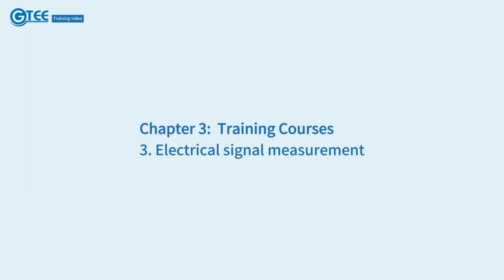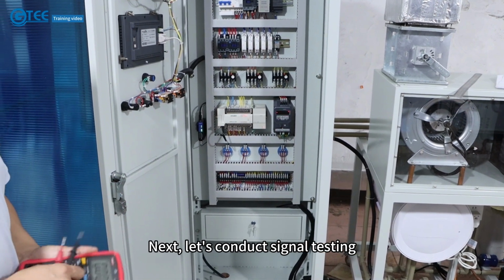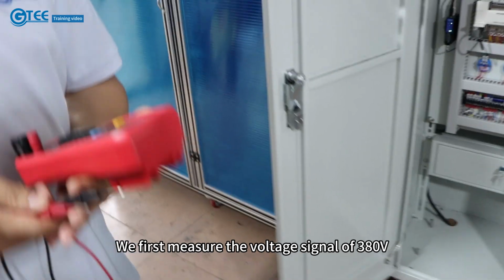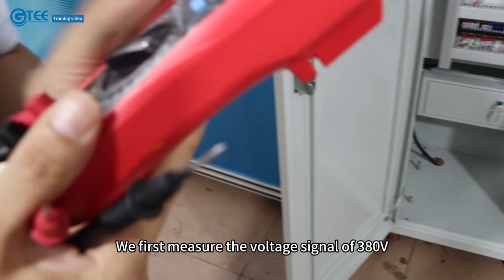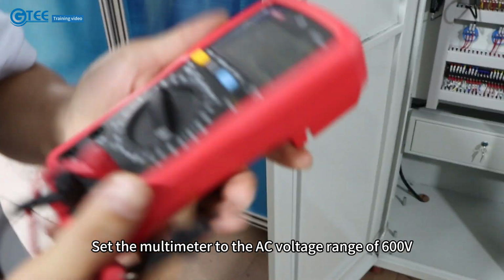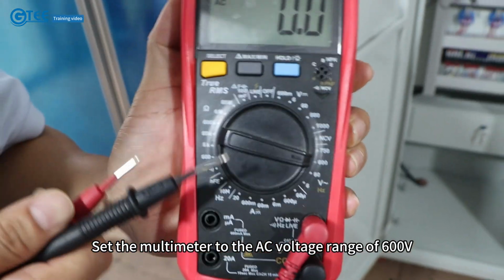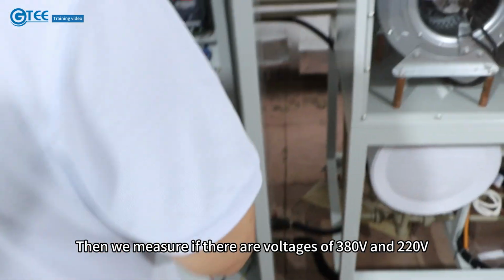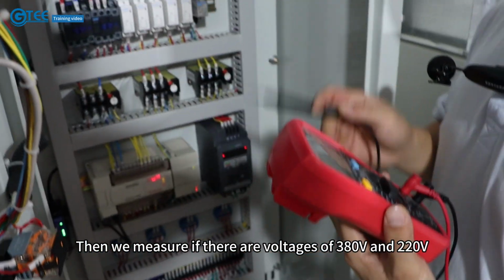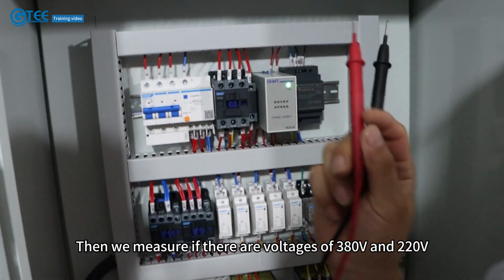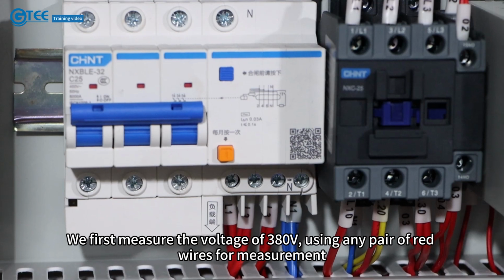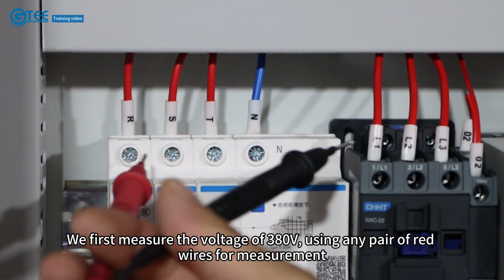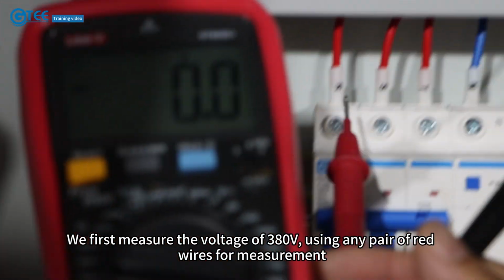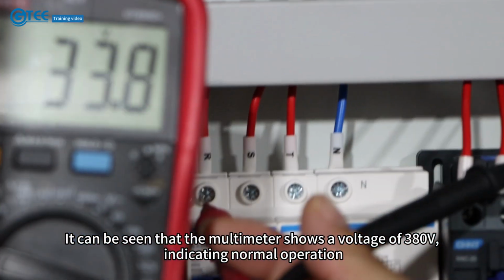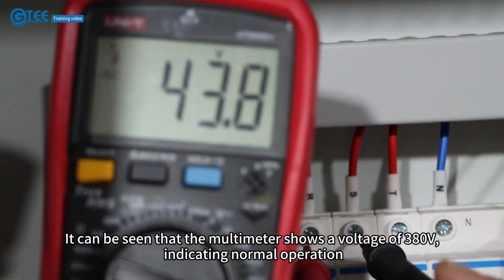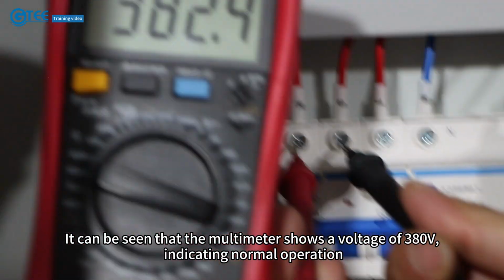3. Electrical signal measurement. Next, let's conduct signal testing. We first measure the voltage signal of 380 volts. Set the multimeter to the AC voltage range of 600 volts. Then we measure if there are voltages of 380 volts and 220 volts. We first measure the voltage of 380 volts using any pair of red wires for measurement. It can be seen that the multimeter shows a voltage of 380 volts, indicating normal operation.